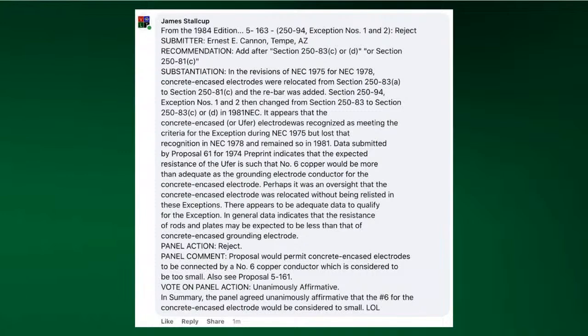And what they said was the proposal would permit concrete encased electrodes to be connected by a number 6 copper conductor, which is considered to be too small. And they send you back to the proposal that was made in conjunction with this, and they voted unanimously affirmative. And in summary, they told you the panel agreed unanimously affirmative that the number 6 to the concrete encased electrode would be considered too small.